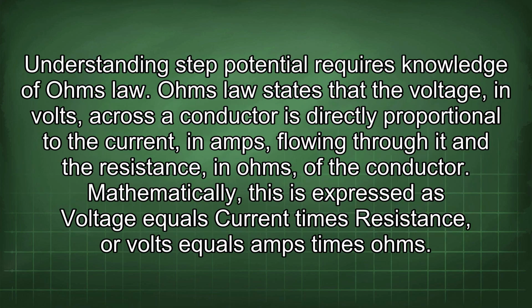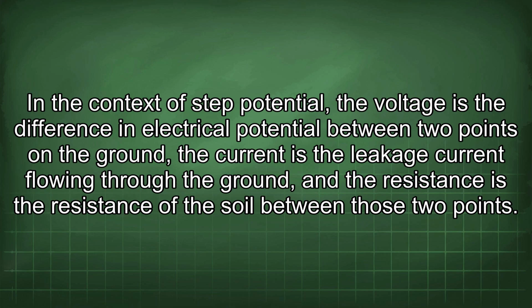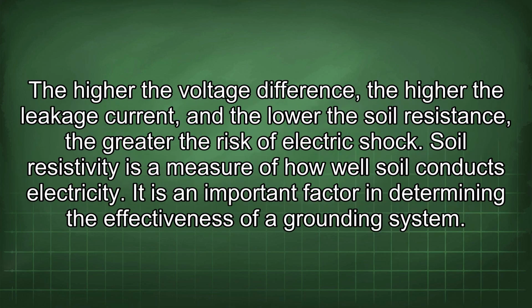Understanding step potential requires knowledge of Ohm's law. Ohm's law states that the voltage, in volts, across a conductor is directly proportional to the current, in amps, flowing through it and the resistance, in ohms, of the conductor. Mathematically, this is expressed as voltage equals current times resistance, or volts equals amps times ohms. In the context of step potential, the voltage is the difference in electrical potential between 2 points on the ground, the current is the leakage current flowing through the ground, and the resistance is the resistance of the soil between those 2 points. The higher the voltage difference, the higher the leakage current, and the lower the soil resistance, the greater the risk of electric shock.